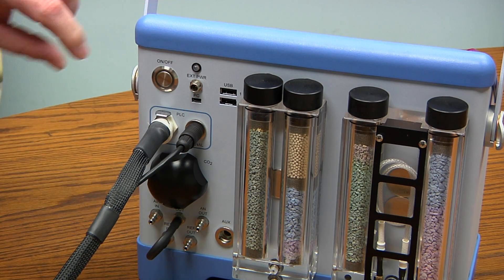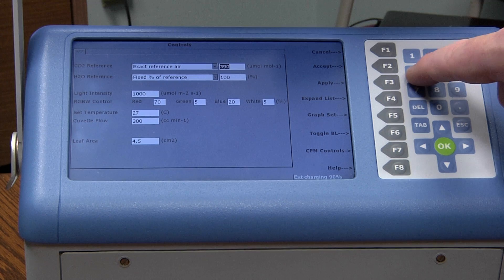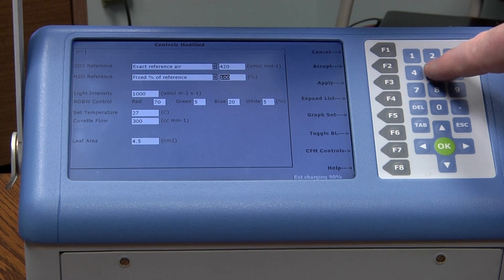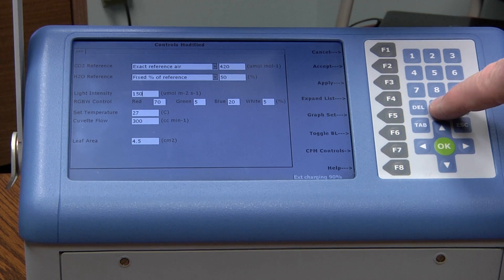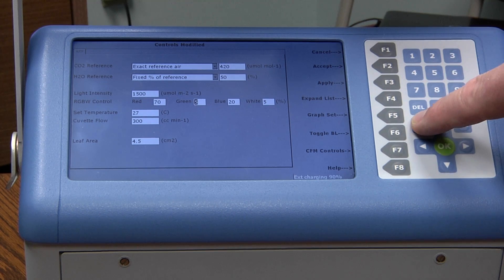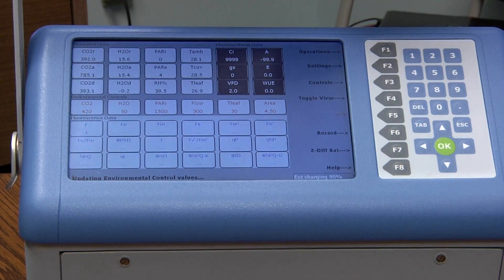Next, connect the leaf cuvette to the CIRAS-3 and power up the system and allow it to warm up. When ready to begin, users typically set up the environmental controls required for measurements. Setup is quick and easy — users can program all environmental controls from just one screen. Simply tab to each control variable, set accordingly, and press F2 to accept the settings. You are now ready to go.